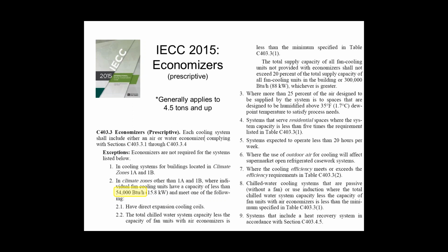Because remember, this rule applies to everything. And if you want to put a nice 95% efficient furnace in a small office building here with a split residential condensing unit, to put an economizer on a residential split system, you have to buy and/or build some kind of economizer box with your own dampers and field install your own controls. And it ends up being like a $1,200 adder to a furnace that probably barely cost that. So it wasn't really practical, cost-wise, for those small non-packaged systems. But yeah, Mark, if you've got a rooftop unit, a 3 or 4 ton rooftop unit, I would still put an economizer on it. It'll pay itself back in that scenario. But on a split system, maybe not.